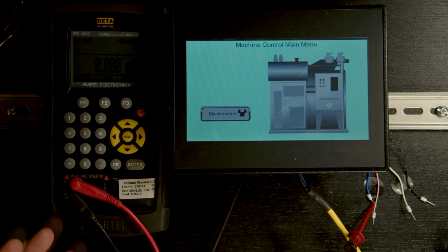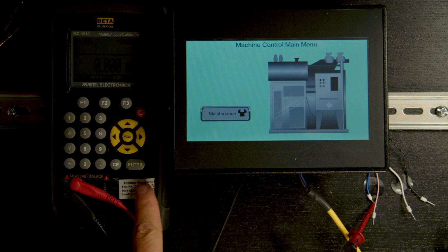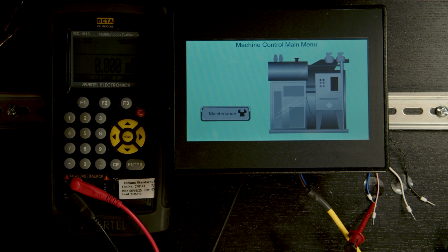machine builders. But it has to be, again, a quality source that can provide a trusted value for you to calibrate your equipment with. And as you can tell from this sticker, we regularly send this unit in for validation of its outputs, so that we can maintain traceability and have confidence in the calibration that we do at Horner with this instrument. Okay, so that's the first step, have the proper instrument.